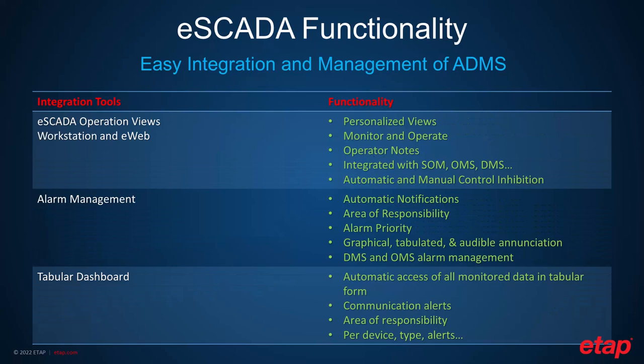The SCADA functionality includes SCADA operation views and web views — personalized views that allow you to monitor and operate the system. It provides operator notes, so if you want to inhibit controls while somebody is doing maintenance, the operator can drop an operator note and automatically inhibit the controls while that maintenance is happening. It is integrated with switching order management, outage management, and distribution management system, and can perform control inhibition automatically or manually.